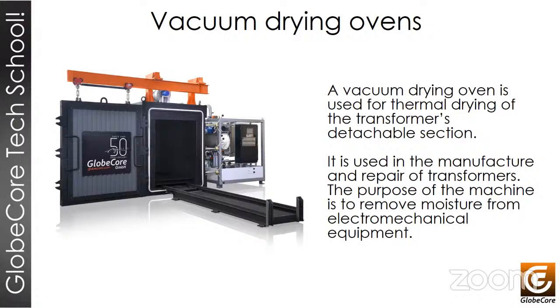Only carefully dried insulating materials ensure a fault-free functioning of high power and high voltage electrical products and slow down the aging process. Materials used for insulation of transformers, such as transformer oils and cellulose, tend to become saturated with moisture.